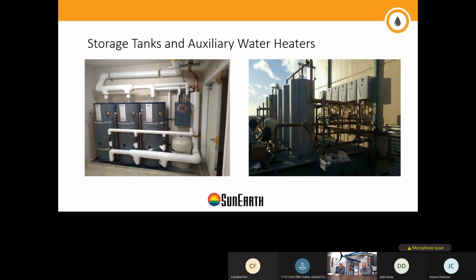So the storage tank, depending on, for instance, if it's rated to be installed outdoor or indoor, depending on retrofit. In new construction, usually all the requirements for the structure are met. Floor plan, if these are going to be above ground, or it's structurally sound. If it's on the ground floor, the footing, the foundation is strong enough, the pad is strong enough to manage these tanks. I mean, if you have an ASME tank of thousands of gallons, there's a footing detail that's done for those, and again, it's all covered in plan.